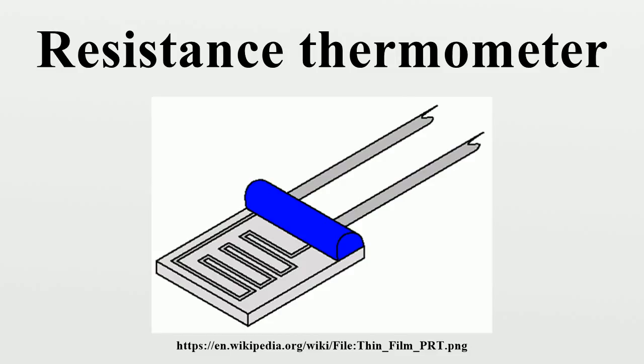3-wire configuration. In order to minimize the effects of the lead resistances, a 3-wire configuration can be used. Using this method, the 2 leads to the sensor are on adjoining arms. There is a lead resistance in each arm of the bridge so that the resistance is cancelled out, so long as the 2 lead resistances are accurately the same. This configuration allows up to 600 meters of cable. As in the case with the 2-wire connection, the usual setting is with R2 equals R3 and R1 around the middle of the range of the RTD.